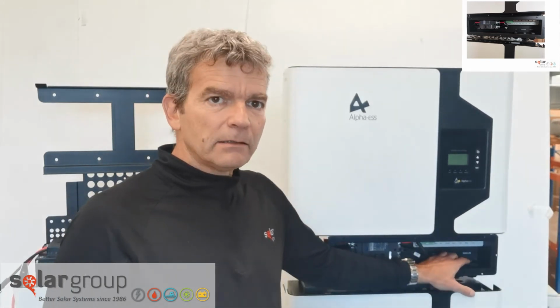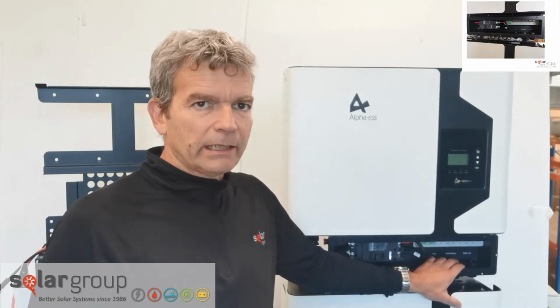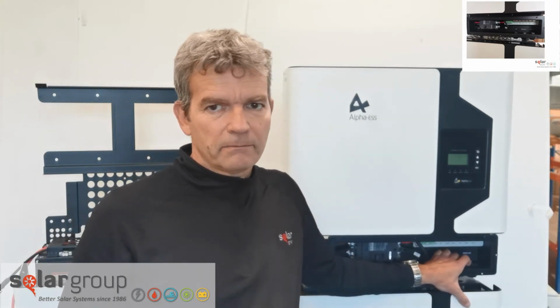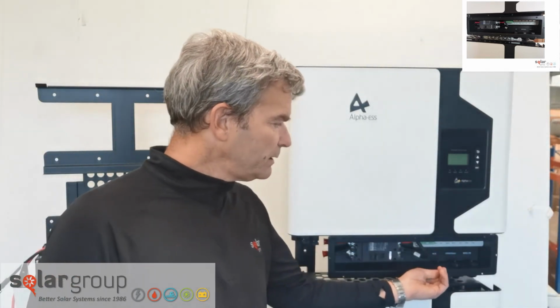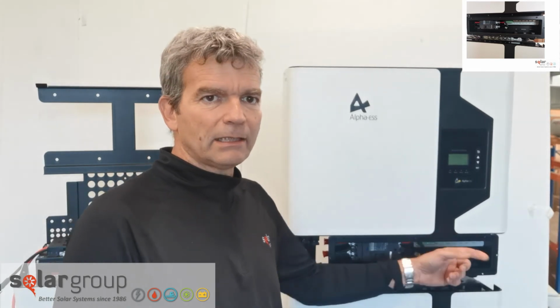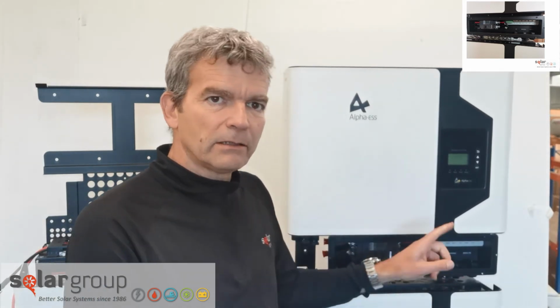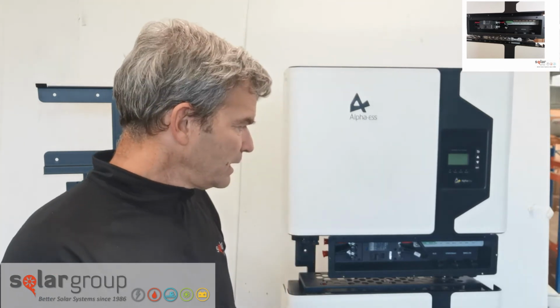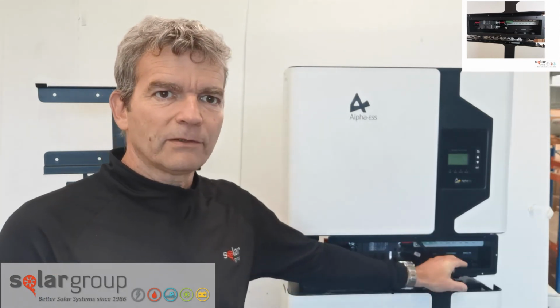The glands here at the bottom cannot take the RJ45 cable. You need to crimp it after you slide it in. So you slide it in and then you crimp it. And of course you can crimp the other side prior to doing that. So that's the only thing you should watch for, so you're not getting yourself frustrated. Crimp it after you slide it through the gland hole.